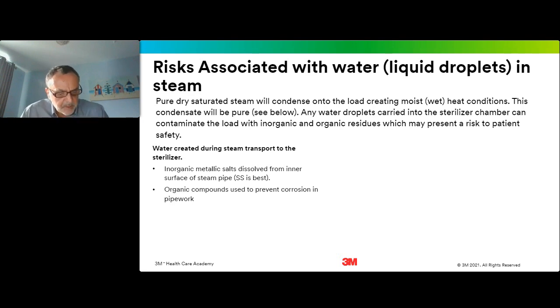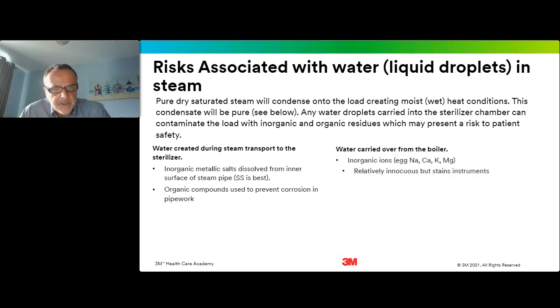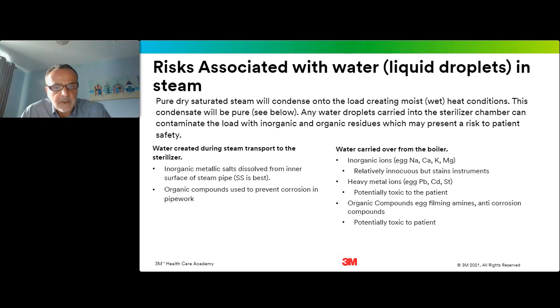And these can be taken up by the condensate as it travels through the steam pipework. And if we don't get rid of that condensed steam before it goes into the steriliser chamber, then it will end up on our loads. We can also have water carried over from the boiler, which I think is probably a much greater problem, because obviously whatever you put into your boiler in terms of feed water, the purity that is, that in turn can be carried over into your steam.